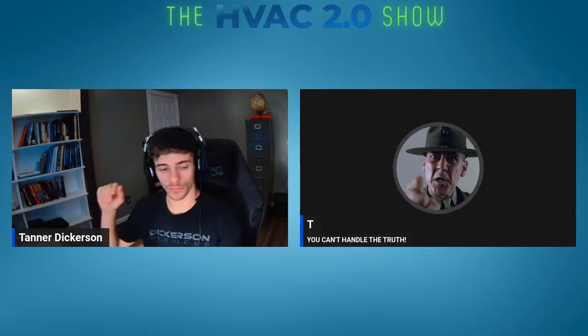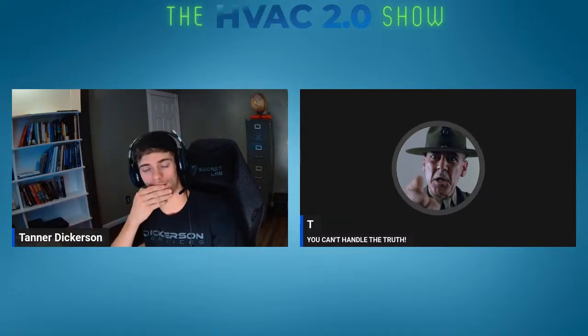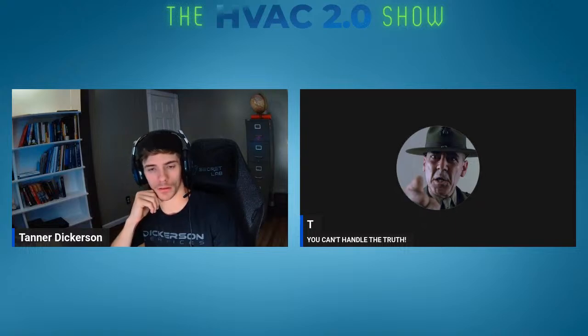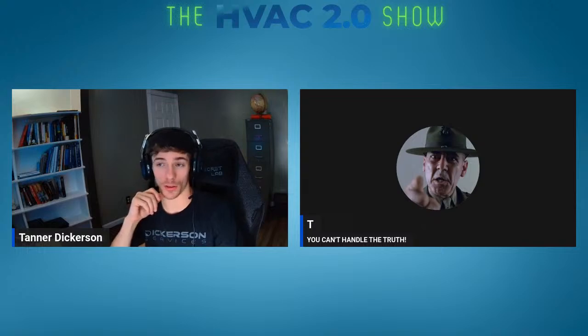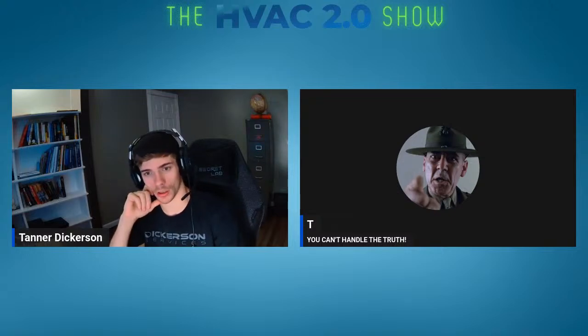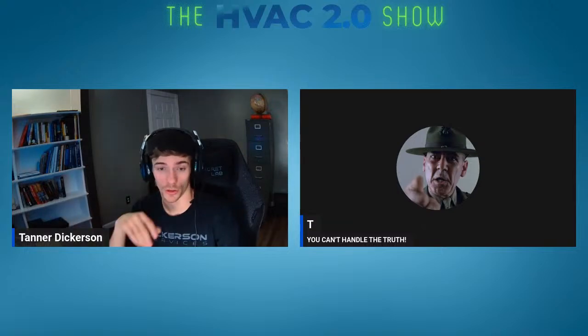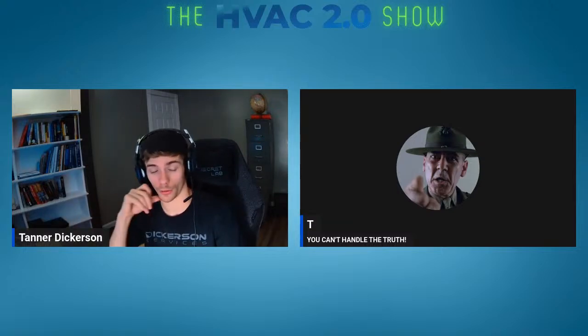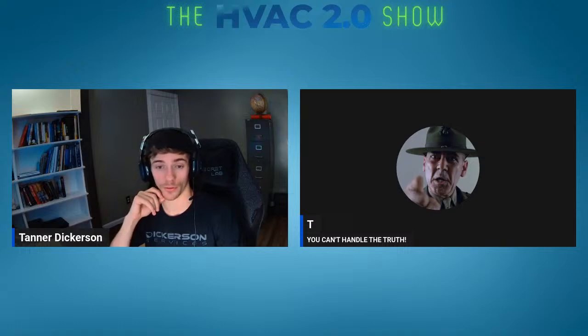And how much would it cost just to do static pressure? $250, $300? I mean, really not even that. If you spend $300 on a manometer you're getting a good one, like that nice new single channel micromanometer from Retrotec, that's the 300-400 range. But if you just wanted to check static pressure and keep it basic, around $100-150 is really all you need.